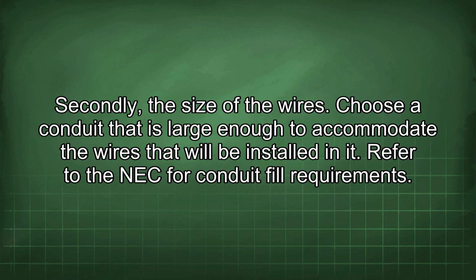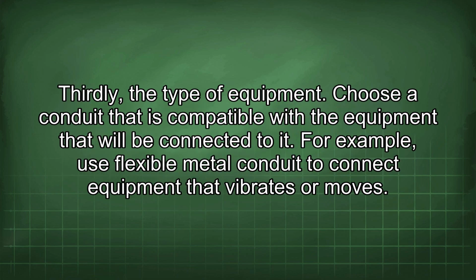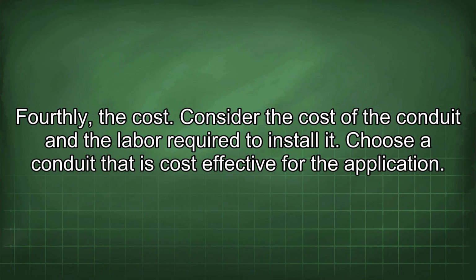Secondly, the size of the wires. Choose a conduit that is large enough to accommodate the wires that will be installed in it. Refer to the NEC for conduit fill requirements. Thirdly, the type of equipment. Choose a conduit that is compatible with the equipment that will be connected to it. For example, use flexible metal conduit to connect equipment that vibrates or moves. Fourthly, the cost. Consider the cost of the conduit and the labor required to install it.